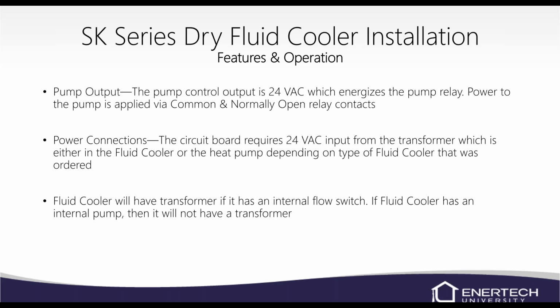Your power connections, the circuit board requires 24-volt input from the transformer, which is either in the fluid cooler or the heat pump, depending on the type of fluid cooler that was ordered. So you can get the 24 volts from the heat pump, or you can order the fluid cooler with the transformer in it. If you have a flow switch in the fluid cooler, then you will have a transformer. If you have an internal pump rather than a flow switch, then you will not have a transformer. So if you're going to use the pump that comes with the unit rather than your flow center, then it will not have a transformer. So you'll use the low voltage power from the geo unit to power the circuit board on the fluid cooler itself.